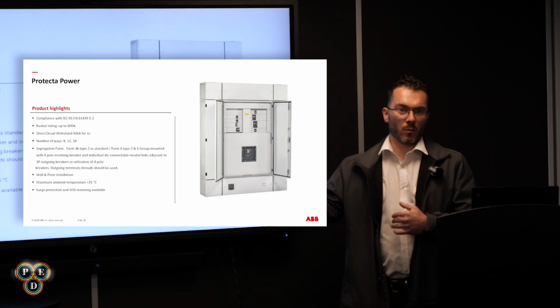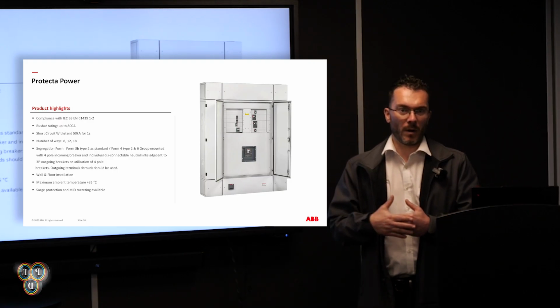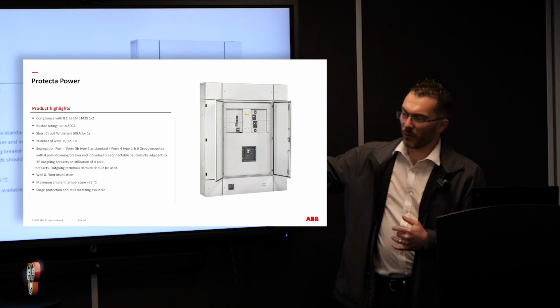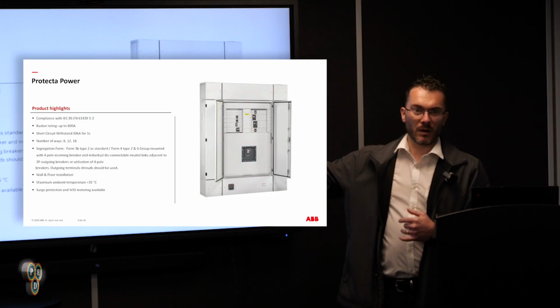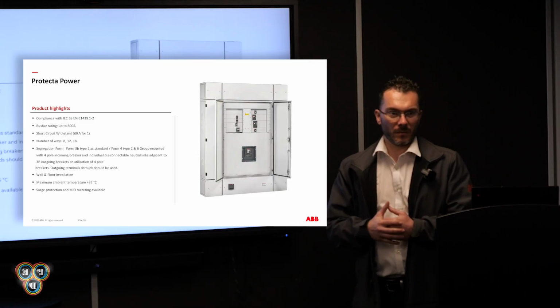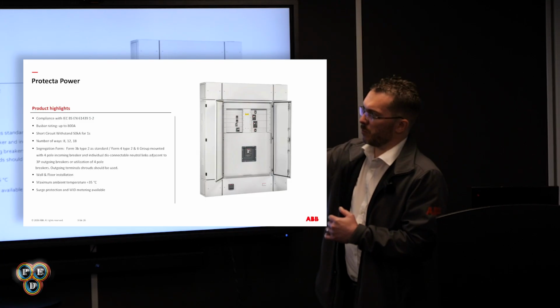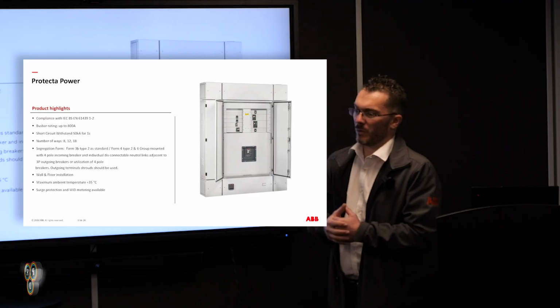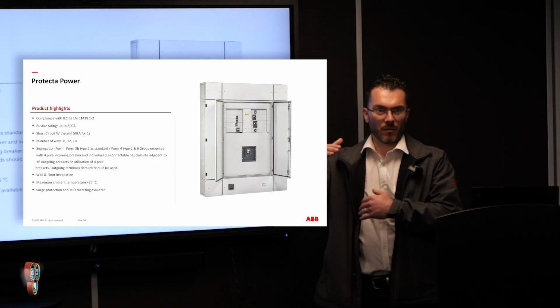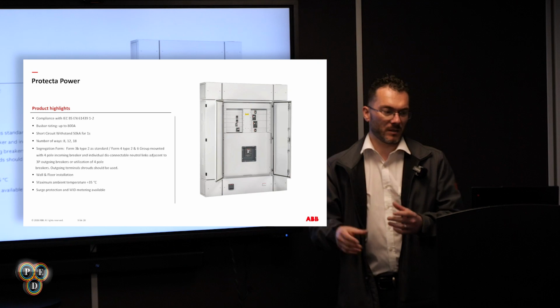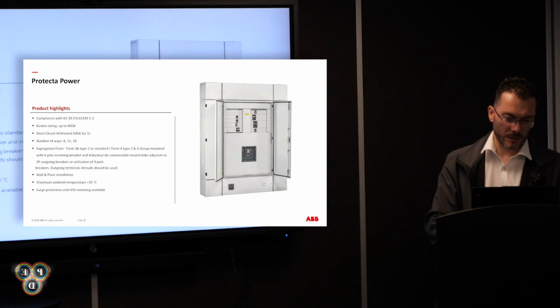So if you went to a Form 4 Type 6, you're going to be using 4-pole devices. You won't fit 8 devices within, or you'll fit a number of devices within the 8-way, but it depends on the size of the current rating and everything else, because it's all based on the frame size of the actual MCCB.